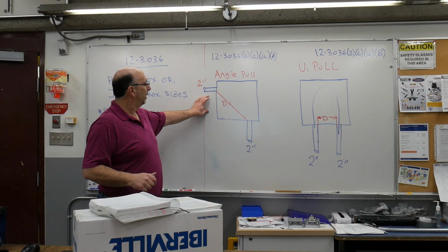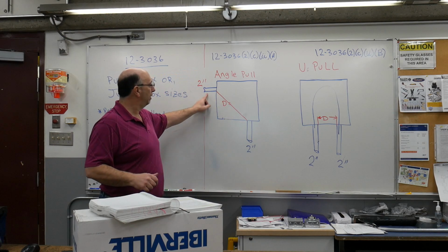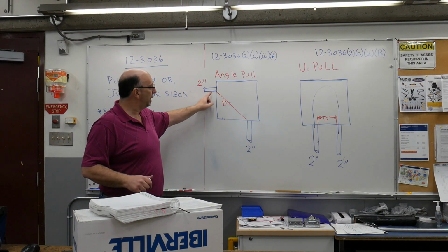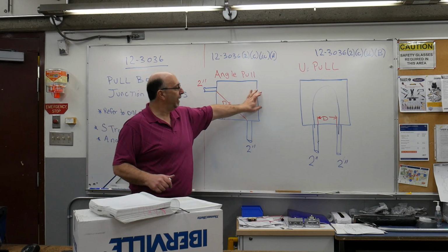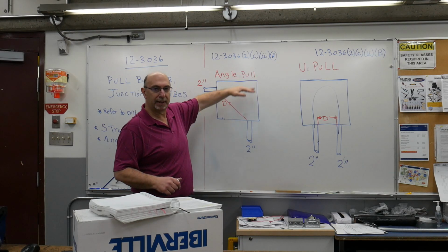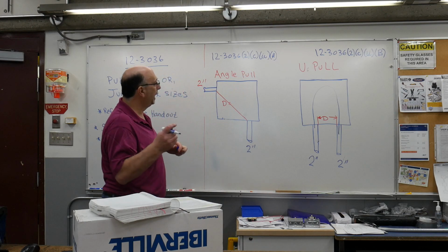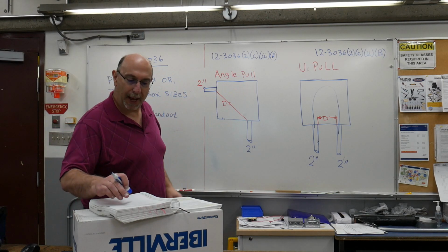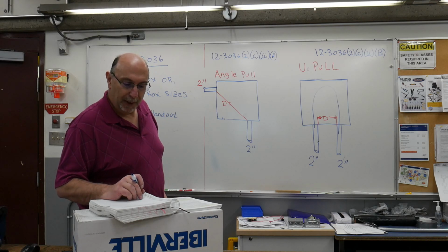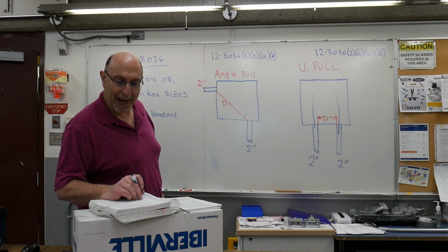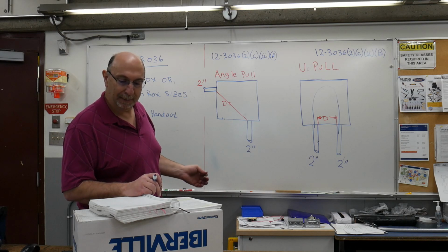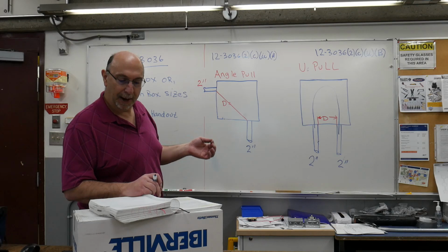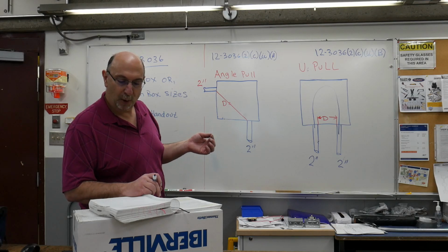We have an angle pull with 2-inch conduit. We want to determine what is this distance between the boxes, and then afterwards we're going to calculate basically the depth of the box. So when you take a look at sub-rule I there, it talks about having a distance, as measured in a straight line between the nearest edge of each raceway or cable entering the enclosure enclosing the same insulated conductors, of at least 6 times the trade diameter of the raceway or equivalent cable.